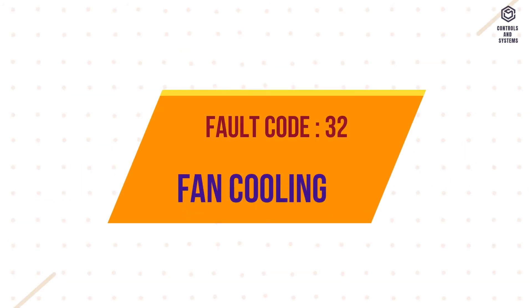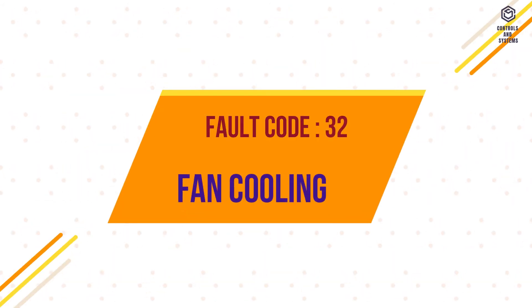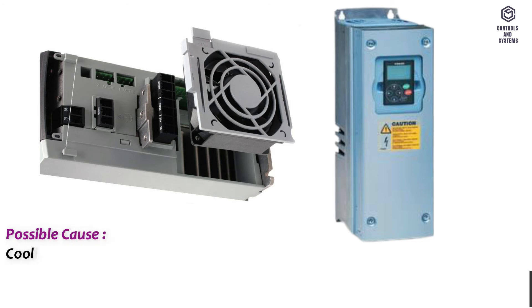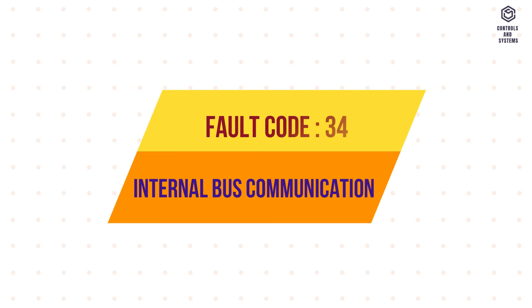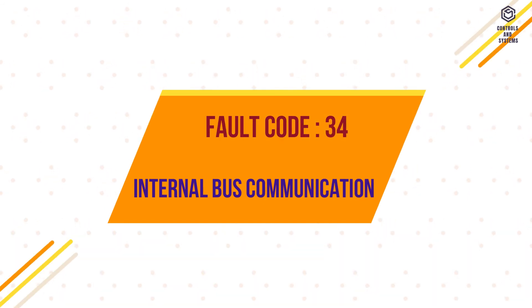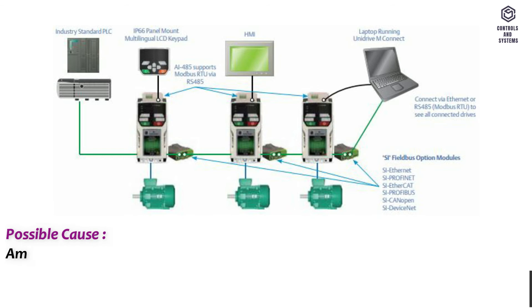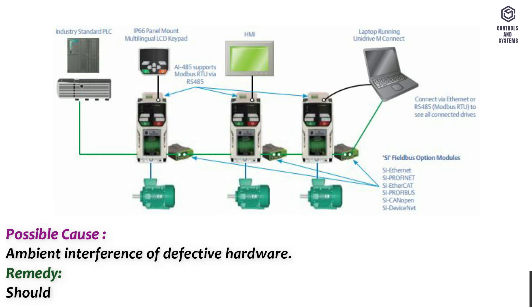Fault code 32 – Fan cooling fault. Possible cause: the cooling fan of the inverter does not start when the on-command is given. Remedy: contact technical support. Fault code 34 – Internal bus communication fault. Possible cause: ambient interference or defective hardware. Remedy: should the fault recur, contact technical support.